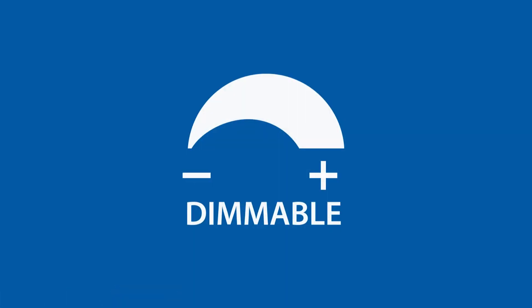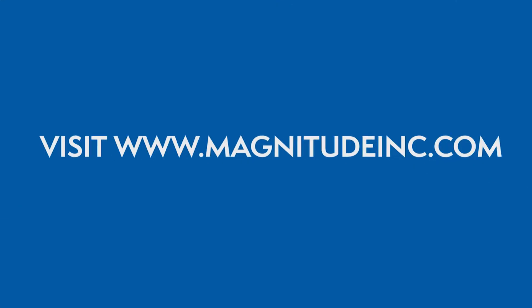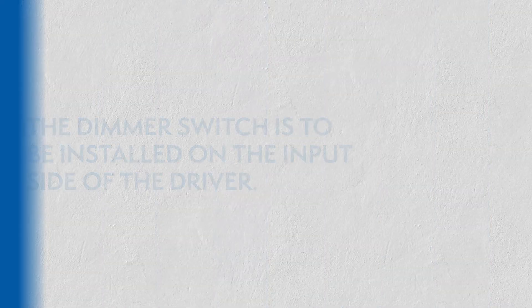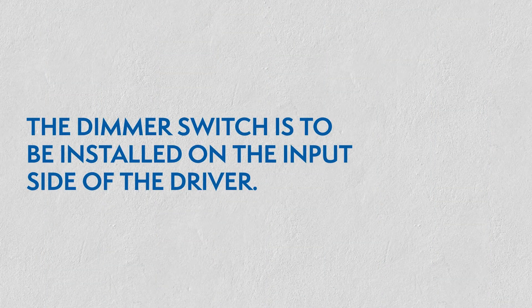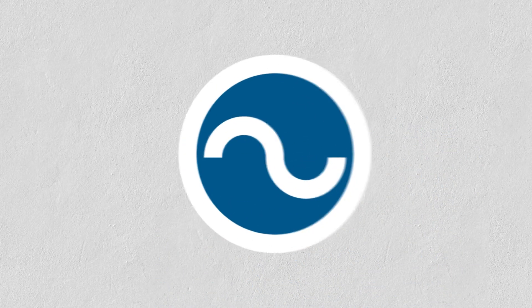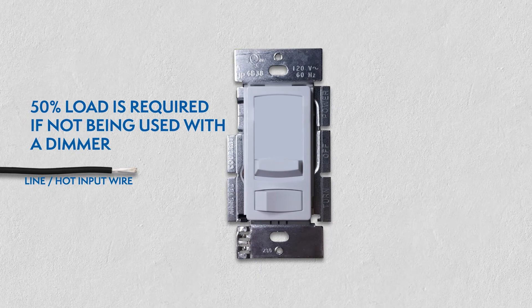Connecting a dimmer. This series of LED drivers are dimmable with any standard MLV/TRIAC leading edge dimmers. Please visit the Magnitude website for a list of compatible dimmers. With the power turned off, the dimmer is to be installed on the input side of the driver at 120V. 50% load is required if not being used with a dimmer.